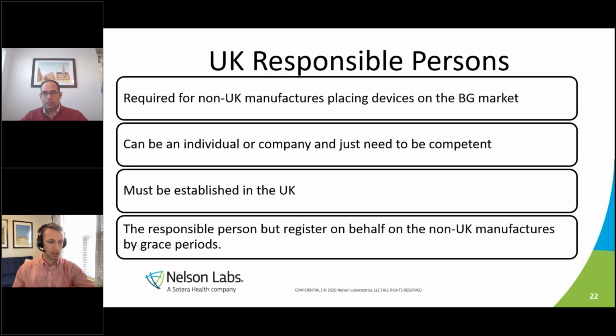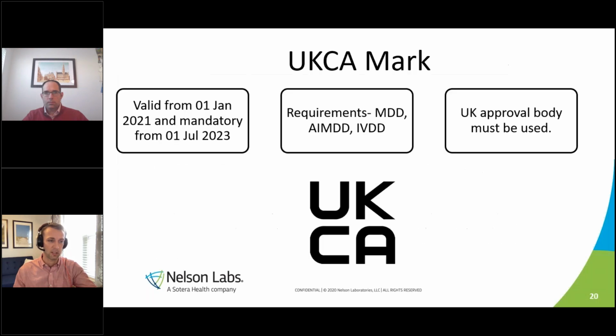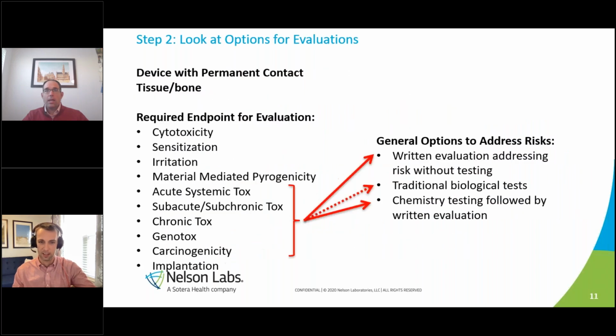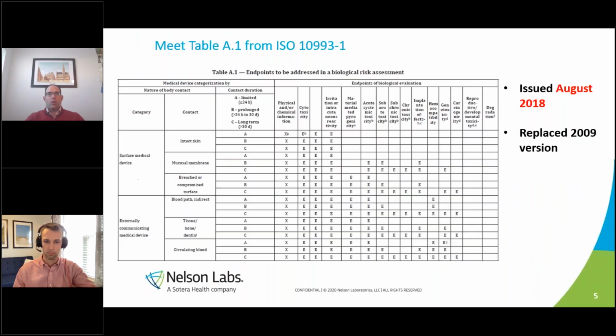Okay. There are a couple more very specific questions, so I'll kind of dive into those a little bit. Maybe we have a few minutes. Which tests of the ISO 10993-1 do we have to apply to our product if it's not intended to be used in direct contact with the patient's skin? It's a class 2A active device, which is not in direct contact with patient's skin, as the patient should wear a t-shirt to use the device on its stomach. Okay, so I'll go back to the chart real fast.